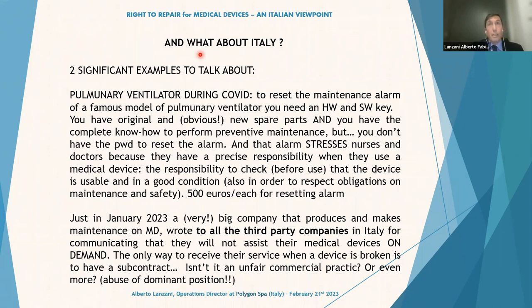It happened that a famous model of a famous brand of pulmonary ventilator was blocked, without the possibility to reset the error message. I had spare parts, original and new, I had all the know-how for making preventive maintenance, but I did not have the password to reset the alarm. So we did preventive maintenance on schedule, but every day the clinicians using the device saw that message and were very worried, anxious and stressed about this condition.